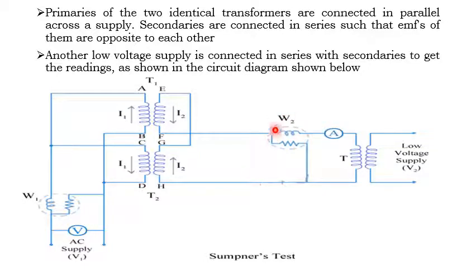A wattmeter W2 is connected across the secondary winding of these two identical transformers, and the ammeter is connected. The secondaries of these two identical transformers, connected in series, are to be connected to the secondary terminal of one more transformer. This transformer is called the low rating transformer. So this is the connection of the Sumpner test on transformer.